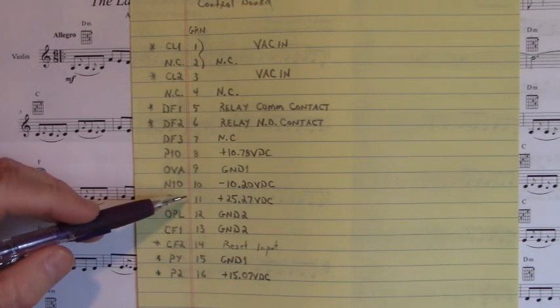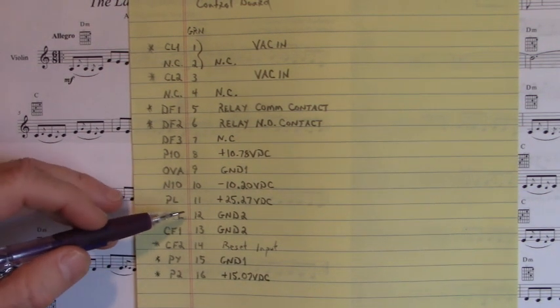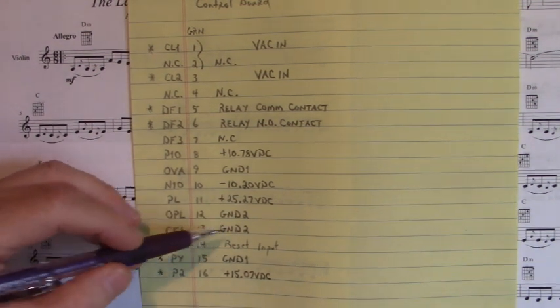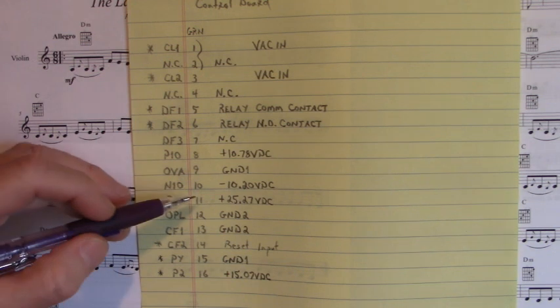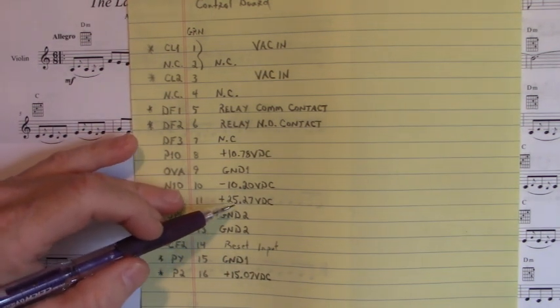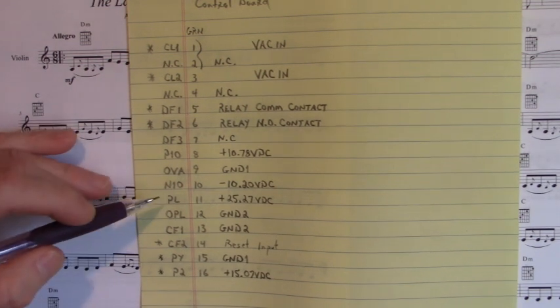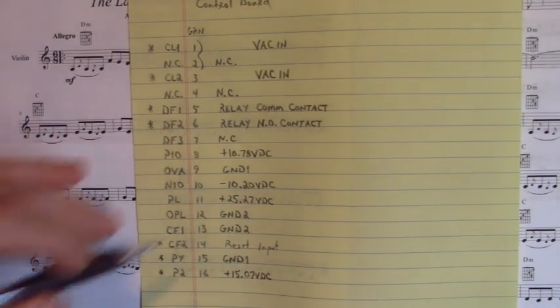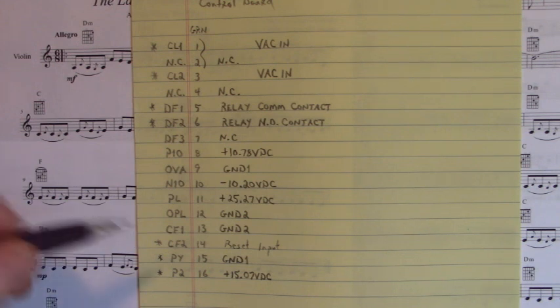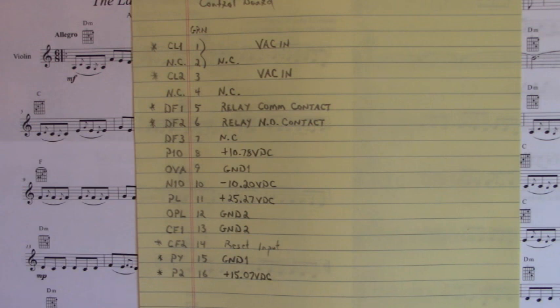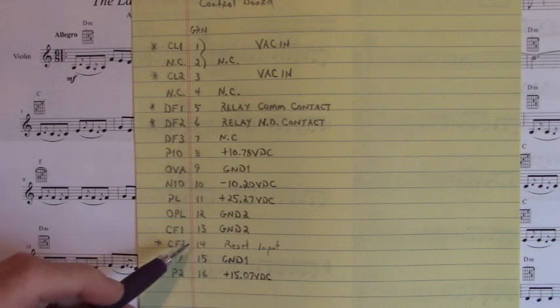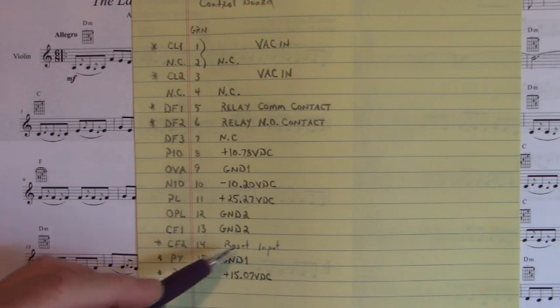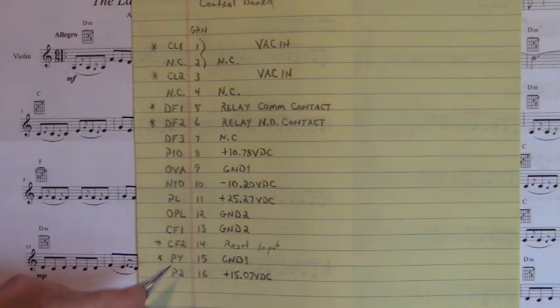Now on terminal 11, reference to 12 and 13, ground 2 and ground 2 here, we have a plus 25.27 volts DC, and I'm thinking that's probably a 24 volt power supply. It floats up to 25.27 unloaded. Now on terminal 14, that's a reset input. I never tagged that input up, so I don't know what we're resetting. Maybe a fault indication or something like that.